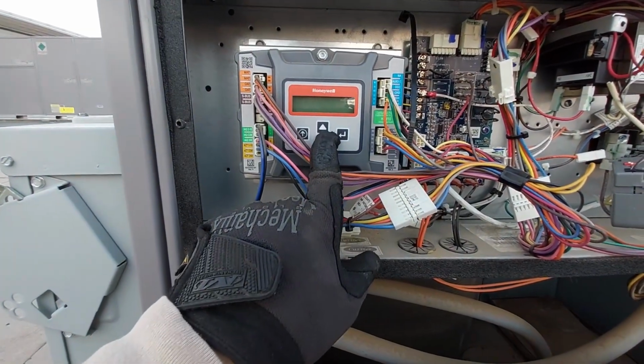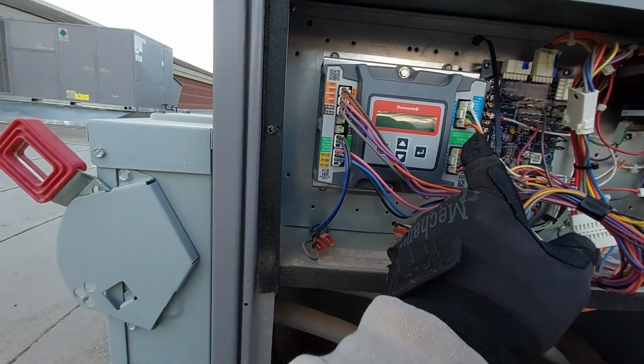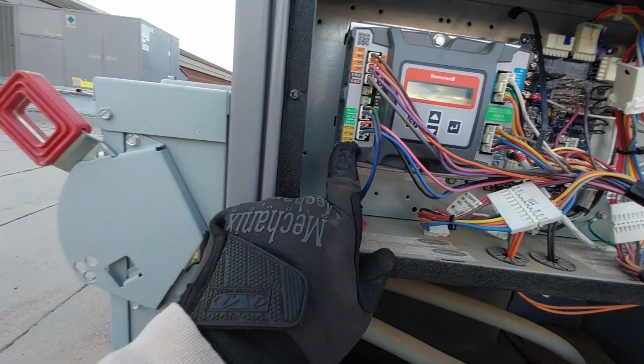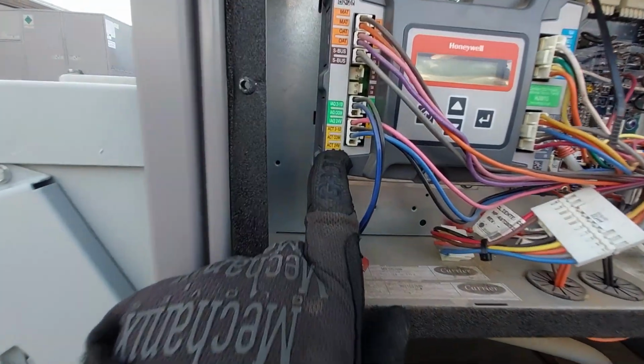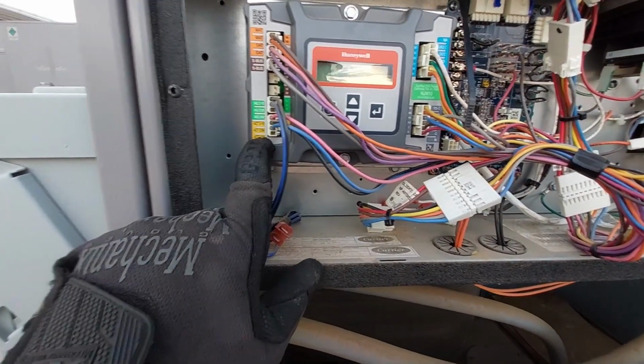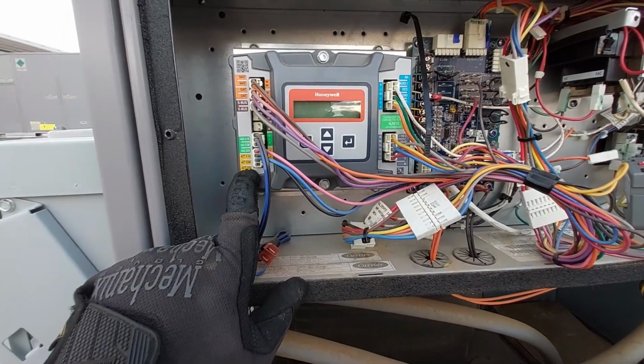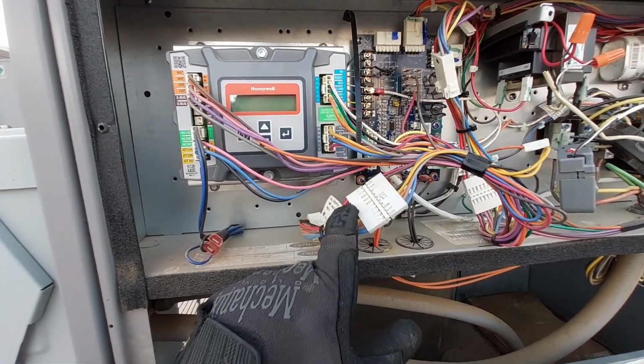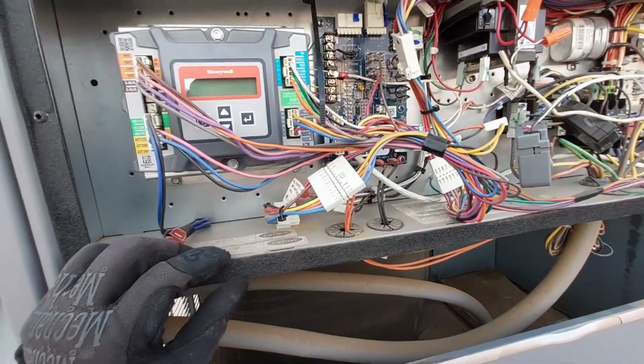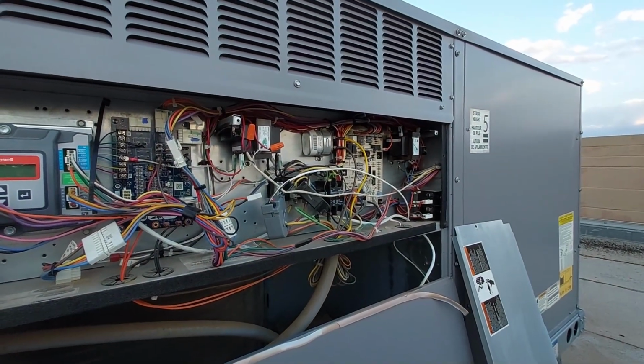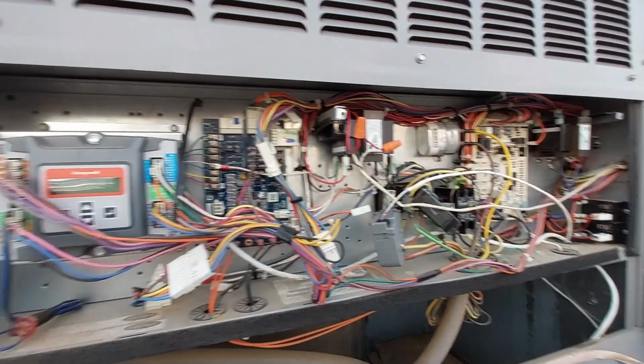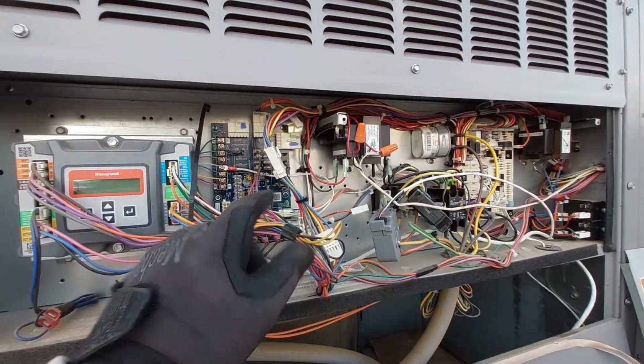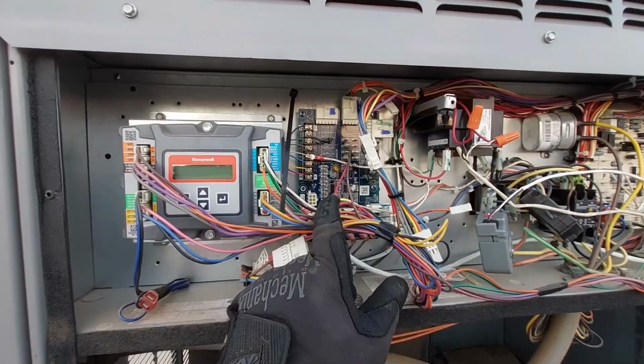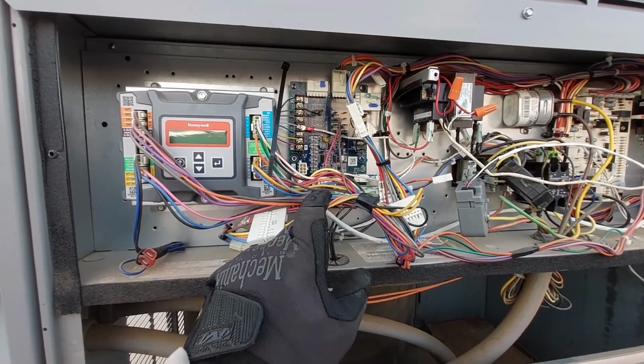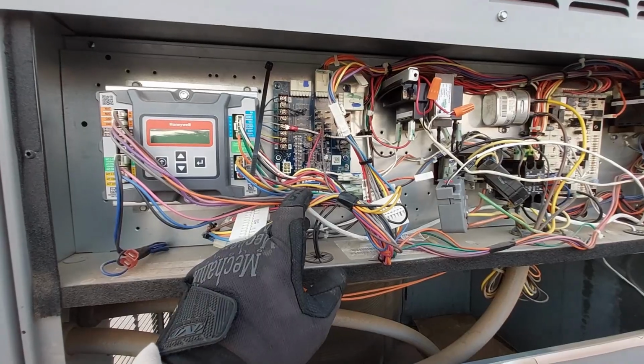So what I'm gonna do, the thing is, I don't really know exactly where the voltage goes in. I'm guessing here, I see 24 volts common. So I'm gonna check this, see if it's getting voltage. If it's not, then I guess I'll trace it back, see where I'm losing my voltage. I know I'm getting high voltage because my blower motor's on, but I don't know if I'm getting low voltage. So I guess I'll check the transformers, see if I'm getting a low voltage out. I'll check my thermostat wires, see if I'm getting voltage there, and go from there.